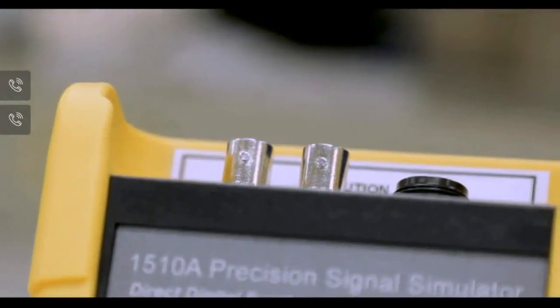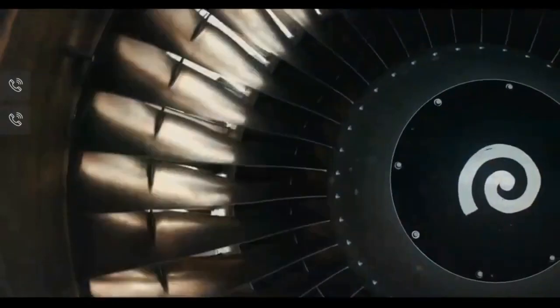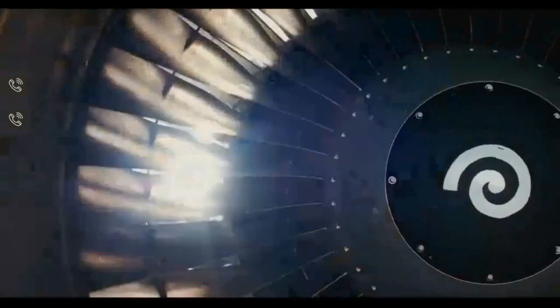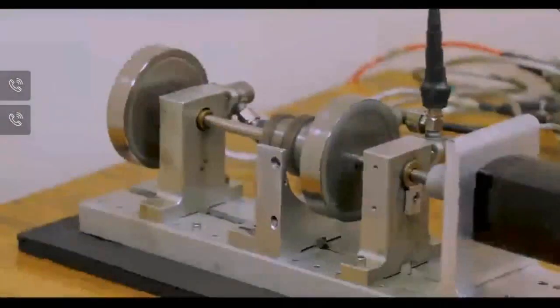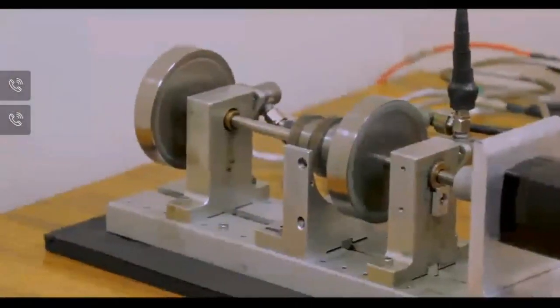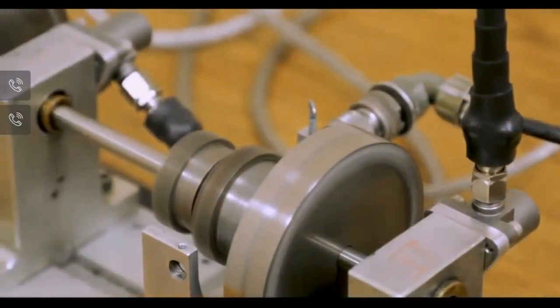The 1510A can create a phase shift between its A and B outputs, such as may be encountered in a rotating system like a jet engine. It can also generate single or odd pulses on the B channel to simulate tachometer pulses.